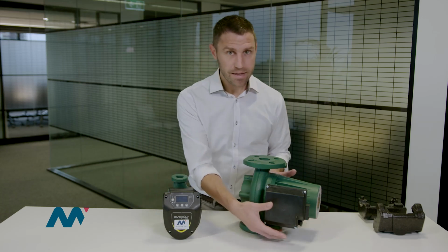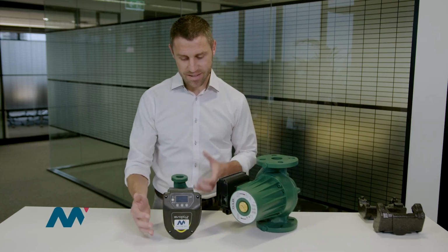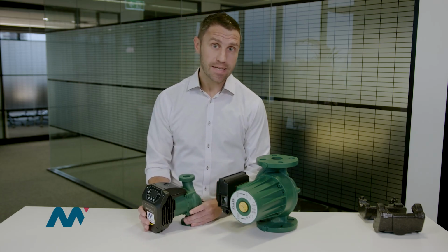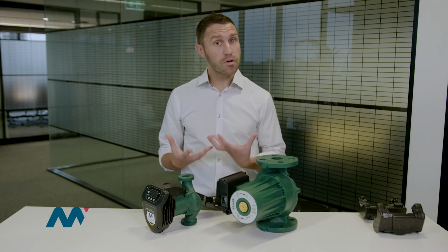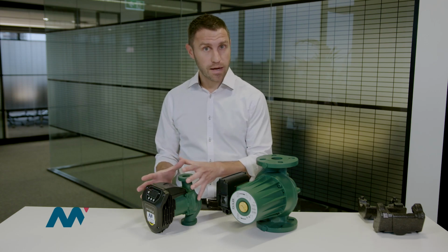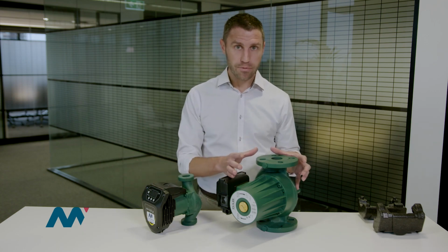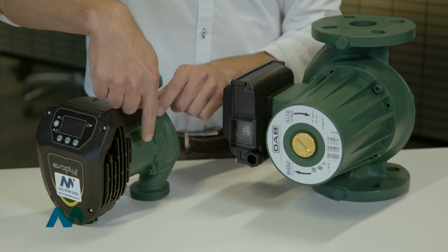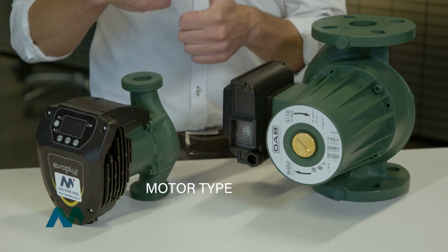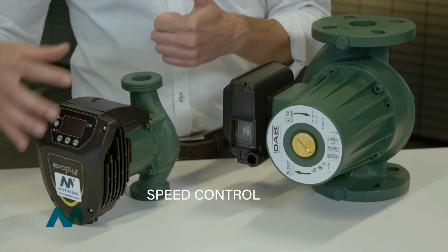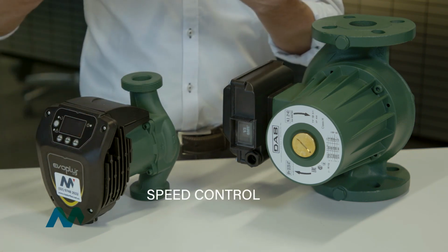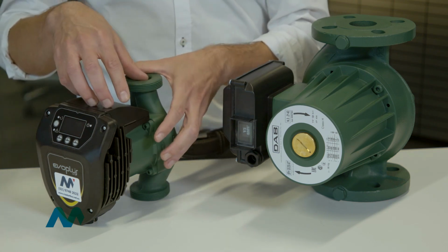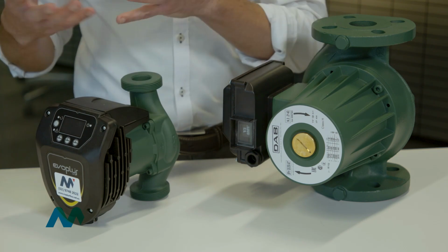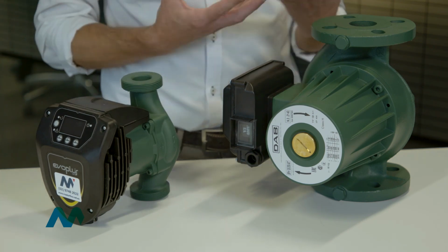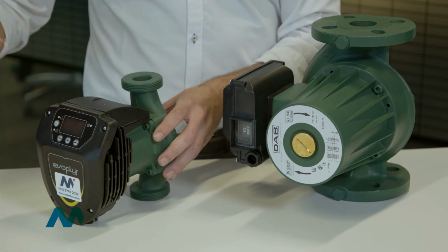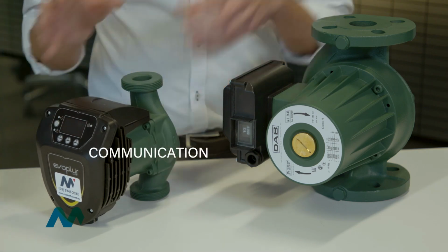So coming back, we put the pump back again in their original position. I summarize here the main advantages, the main points of difference of a variable frequency drive circulator compared to a 3-speed. First of all, synchronous motor, permanent magnetic motor, variable speed control that is necessary to drive a permanent magnetic motor. This also gives us more flexibility on the curves and on the set point, and remote communication with the pump that here is not available.